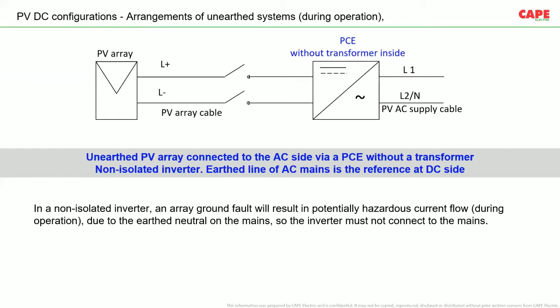In single-phase inverters, in a lot of places, the neutral of the inverter is connected to earth. I have even seen one of the utilities' recommendations. They say that the neutral of the inverter shall be connected to 2 earth pits, which is wrong. Please don't do it. Here, the safety measure is that in case of any fault at the DC side, the incoming supply will be isolated, and this feature must be inbuilt in the PCE. If the PCE lacks this particular feature, of course your solar PV will be in trouble. It can catch fire.